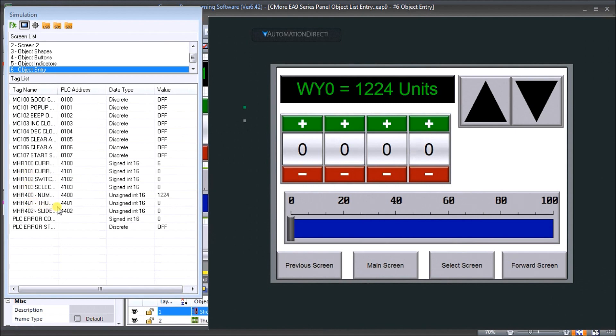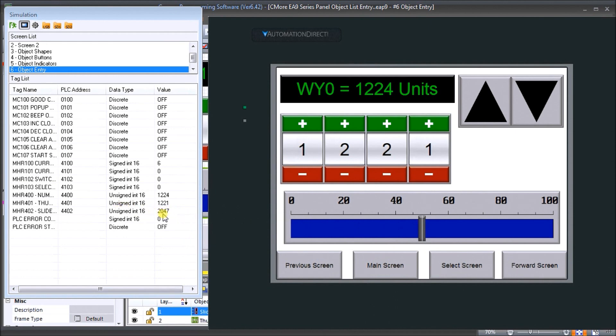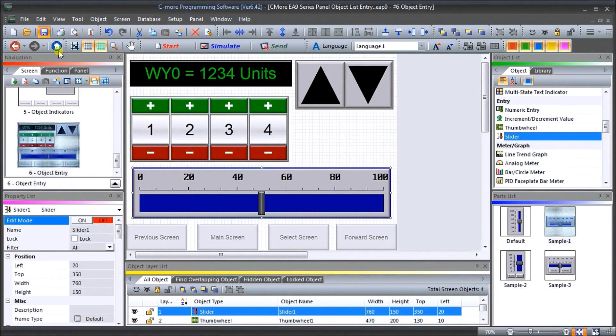Under MHR 401 we have our thumbwheel switch. Adding digits gives us 1221, which is exactly what we see displayed. For our slider, taking it to about half gives us 2047, and the very far end gives us 4095 — exactly what we scaled it for. As I move the slider the corresponding numbers appear. Let's exit the simulation and make sure everything is saved.